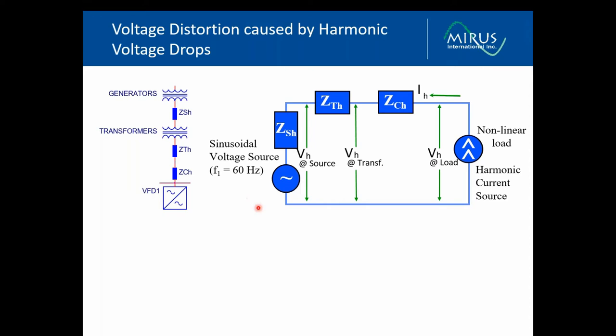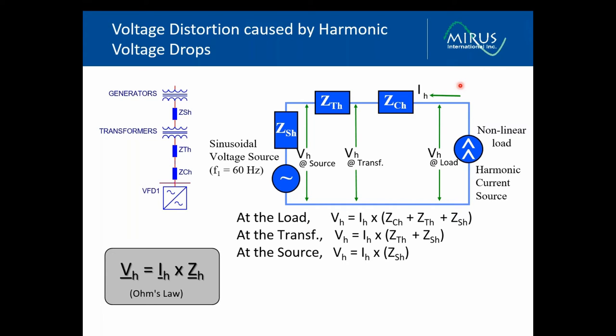The equivalent diagram shown to the right here has the nonlinear loads as a current source of harmonics, injecting harmonics into the power system as these harmonics pass through the impedance of the cables, the transformers, and the source impedance of the generators. And as they do so, Ohm's law says you're going to get voltage drops due to the harmonic currents and the impedance of the power system. So you'll get these voltage drops at each of the harmonic numbers.